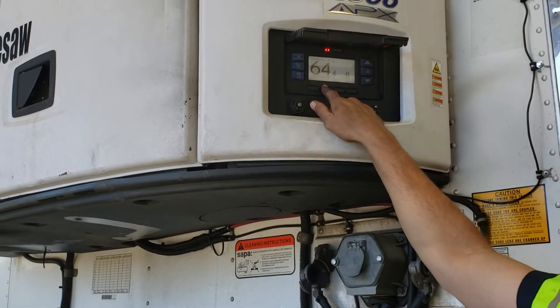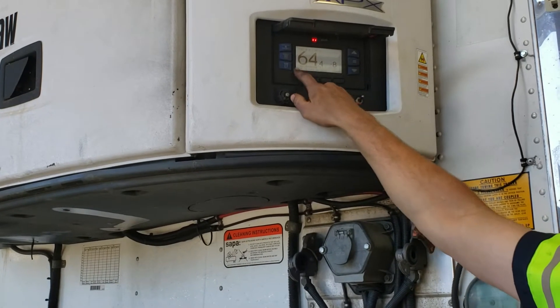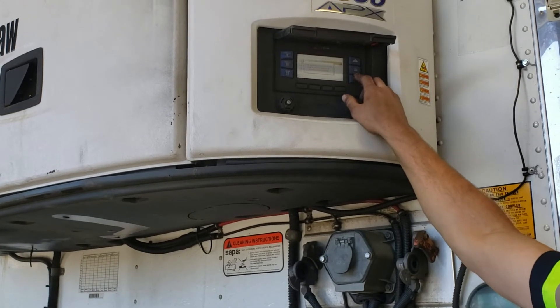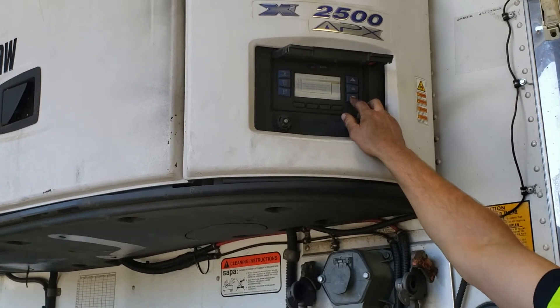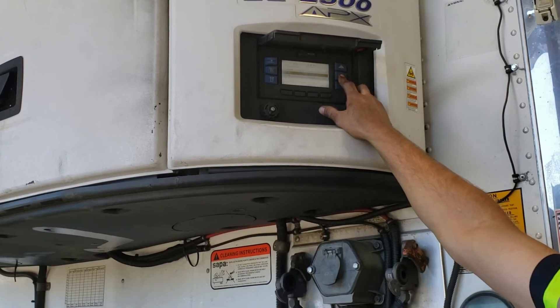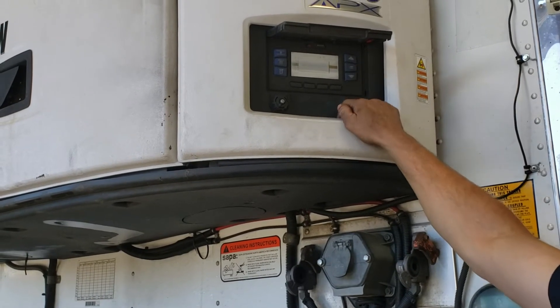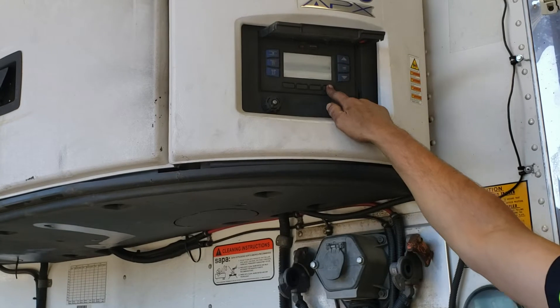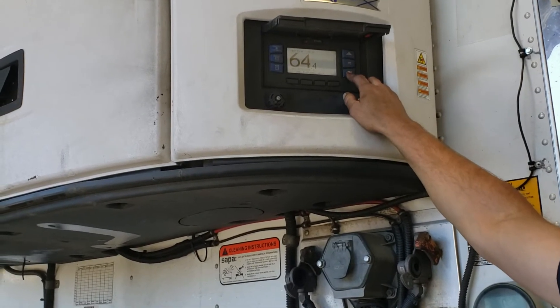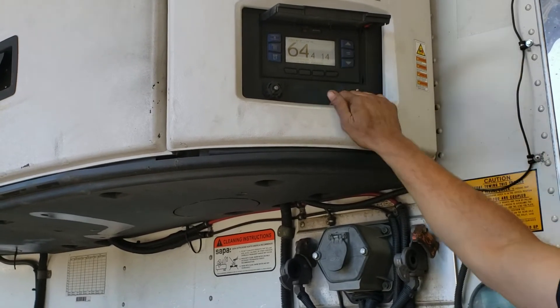At the end of it, it'll tell you if it passed or failed. If it failed, it'll tell you what it failed for. If it passed, then that's great, and you're ready to go to your IntelliSETs to reach your set point — we have name settings in them, but we also have a range of numbers. If you're trying to get a set point between, say, 11 and 24 degrees, go ahead and select that range of numbers, exit the menu, and use your up and down arrows to change it to whatever set point you're trying to get to, and select that equals button.